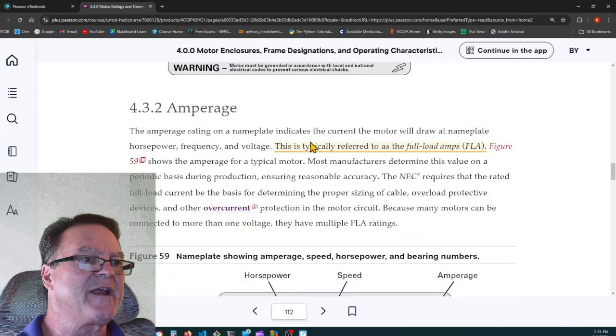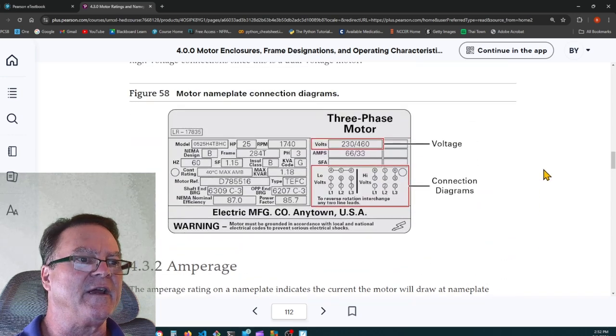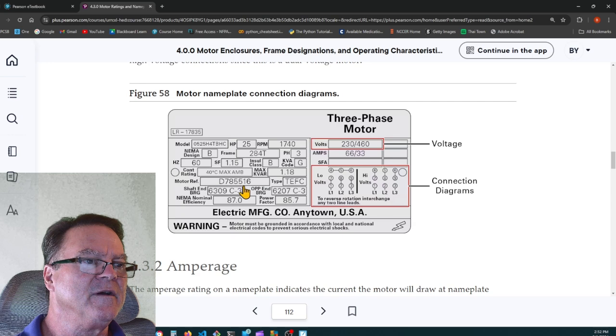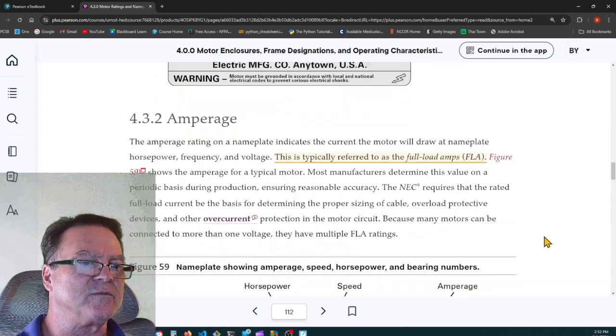The amperage rating on a nameplate indicates the current the motor will draw at nameplate horsepower, frequency, and voltage. So here's a highlight. This is typically referred to as the full load amps, FLA. Let's see if they put that on here. Full load amps. 25 horsepower, 1740 RPM. Service factor of 1.15. Yeah, they didn't put full load amps, they just put amps, 66 or 33. Notice how if you hook it up for 460 volts, it's only going to use half the amperage. We'll discuss that later.